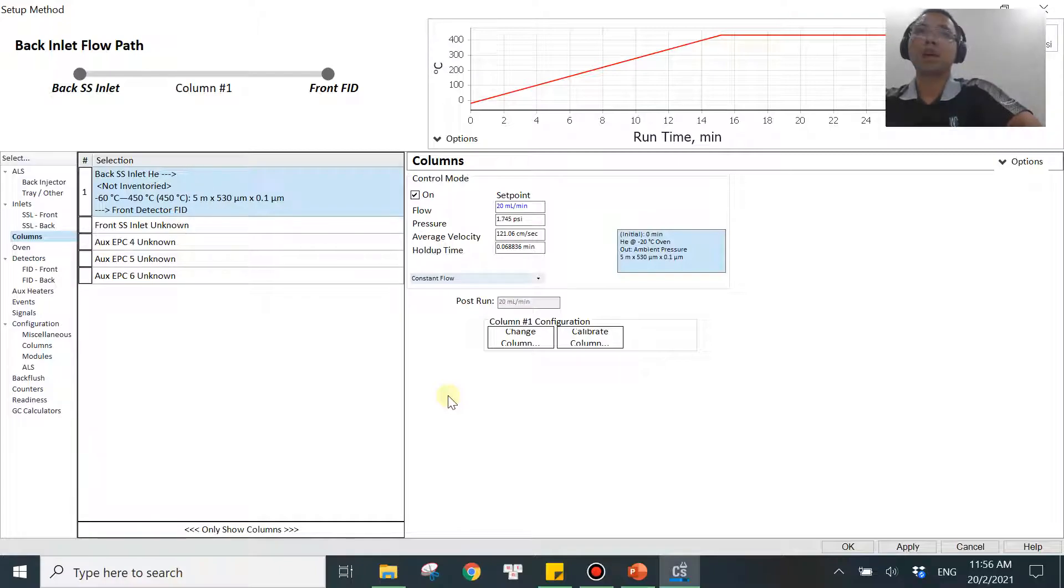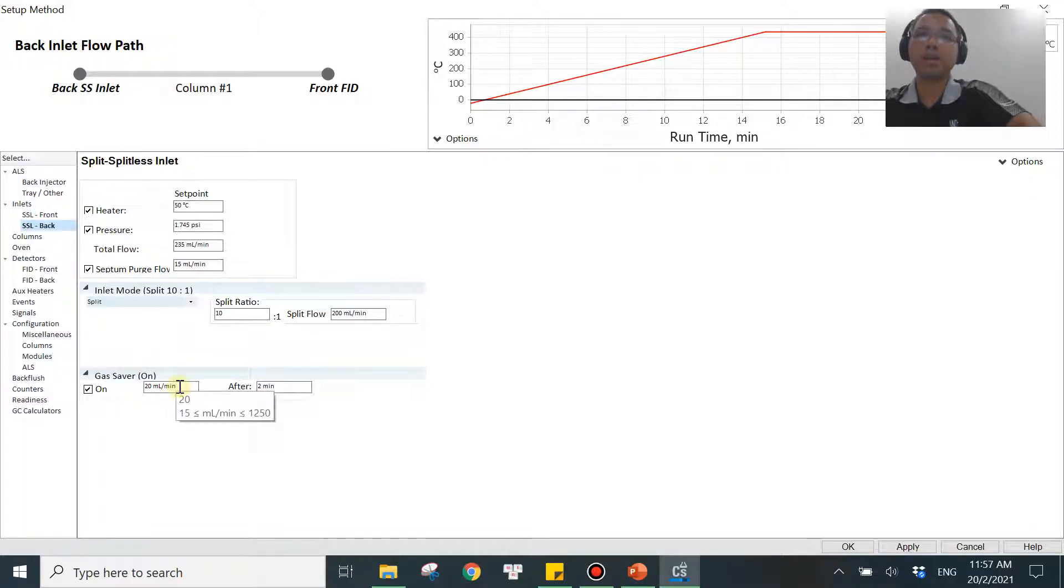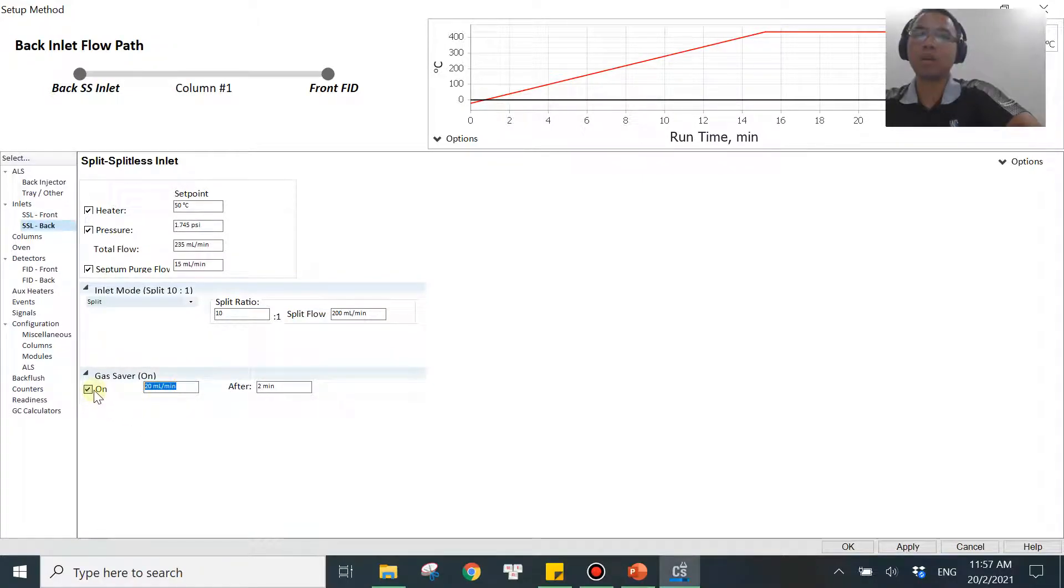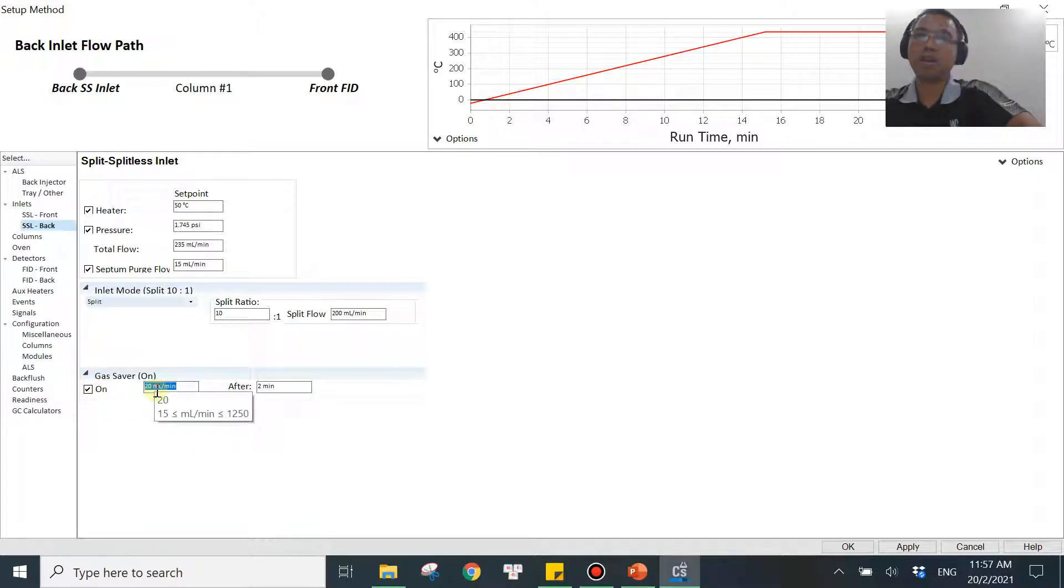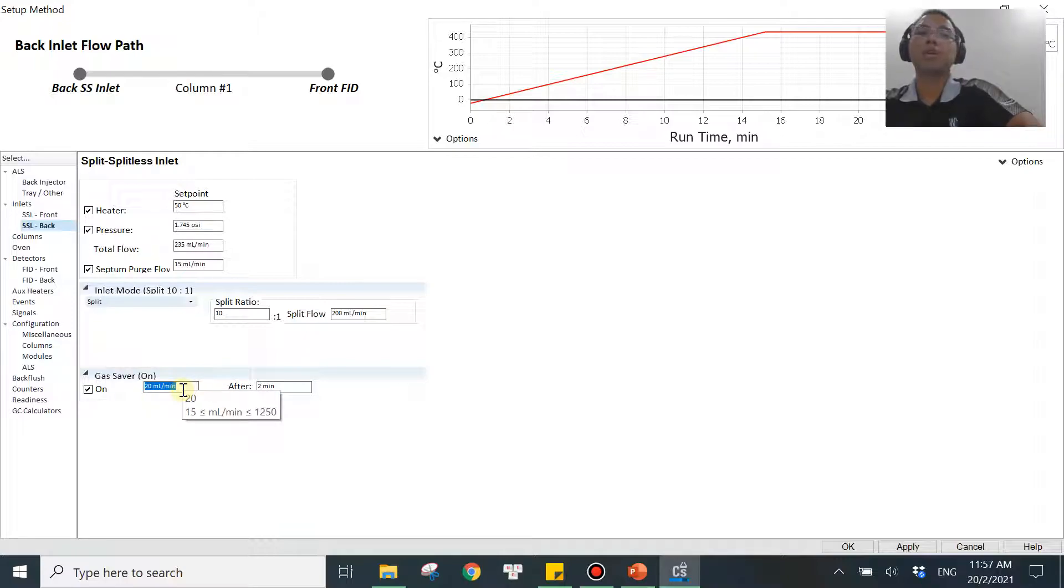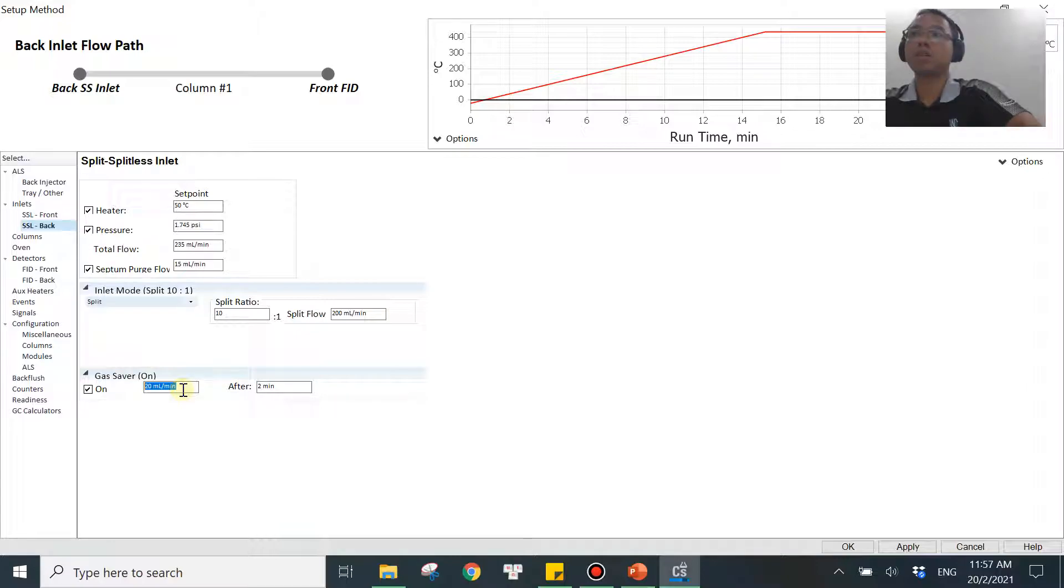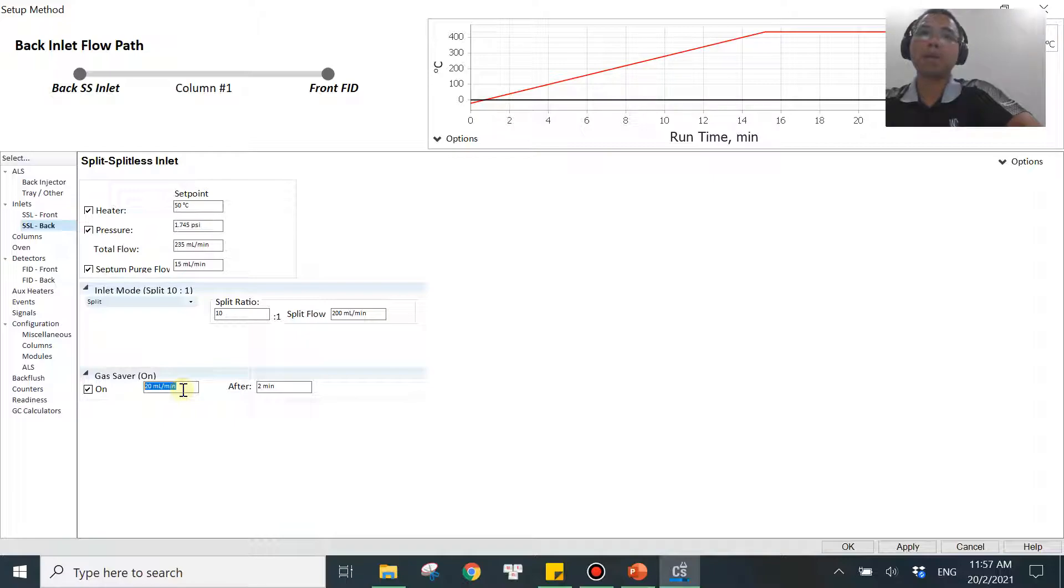So if you are in this scenario, one of the ways that you can do is you can just simply go back to the inlet and increase the flow rate of the gas saver over here. Of course, you don't want to turn it off because you want to save gas. But you don't want to shut down your GC either, right? So instead of 20, you might do a few experiments to try. Let's say you can go like 30, 40, 50, something like that to try. So one of the GCs that I experienced with this one, I have to increase the gas saver flow to, if I remember correctly, it was 50 mL per minute for me to keep the pressure sustainable during the run. Otherwise, once in a while, it would just shut down the GC because the pressure was not enough to catch up with the oven ramping. So that's one case that you want to keep in mind in case you want to set up the gas saver correctly.